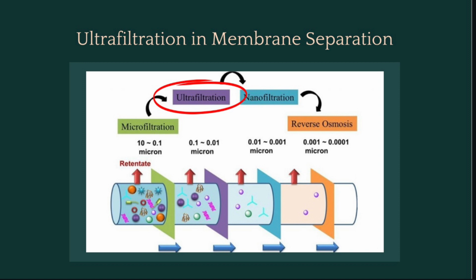This process is based on a porous ultrafiltration membrane with openings that are between 0.01 and 0.1 microns. For reference, 1 micron or 1 micrometer is equal to 0.001 millimeter. This makes the porous openings in the ultrafiltration process as small as 0.00001 millimeter to 0.0001 millimeter.